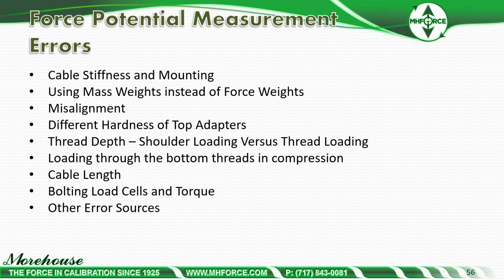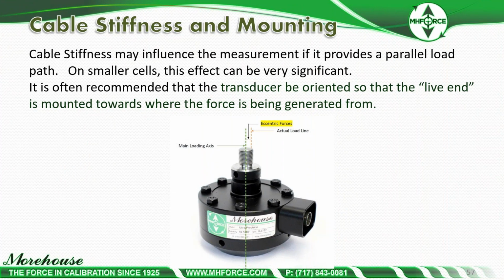Right now we're going to start looking at all these different errors, and the first one is cable stiffness and mounting. Cable stiffness may influence the measurement as it can provide a parallel load path. On smaller cells, this effect can be very significant. It's often recommended that the transducer be oriented so that the live end is mounted toward where the force is being generated. This is the live end of this transducer.